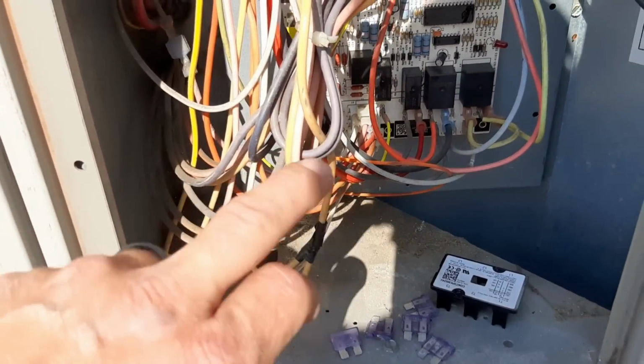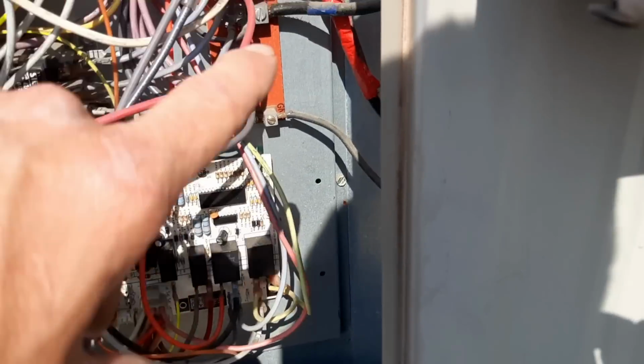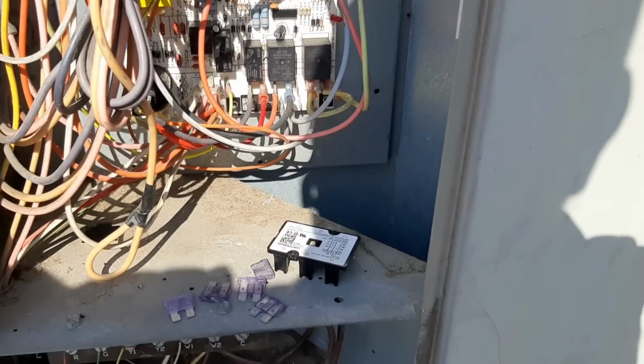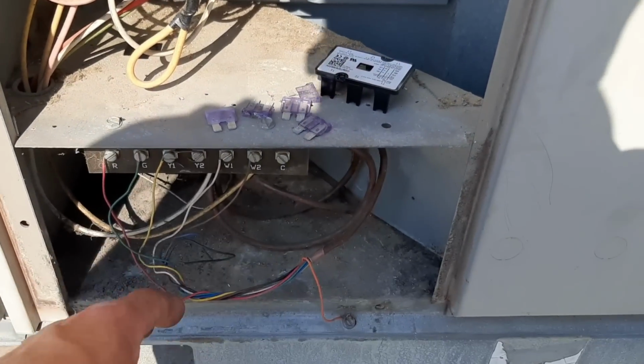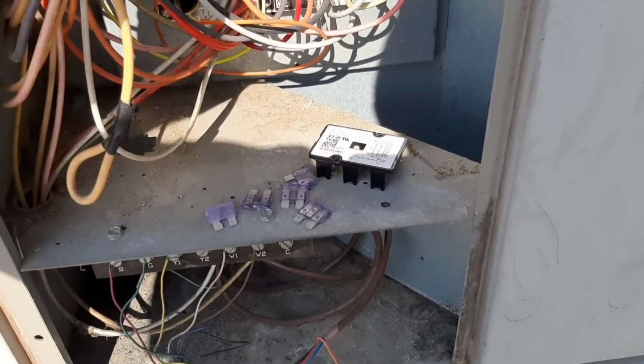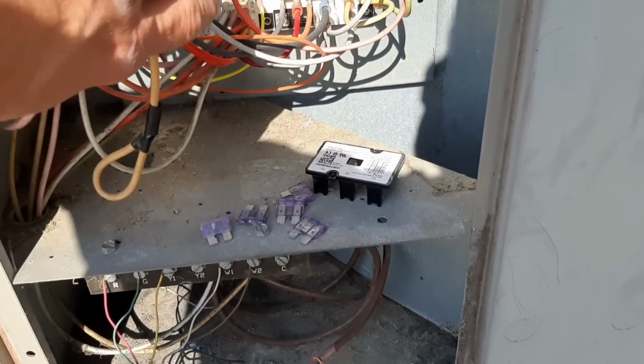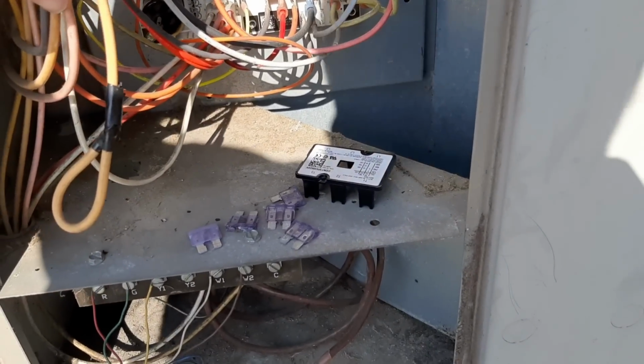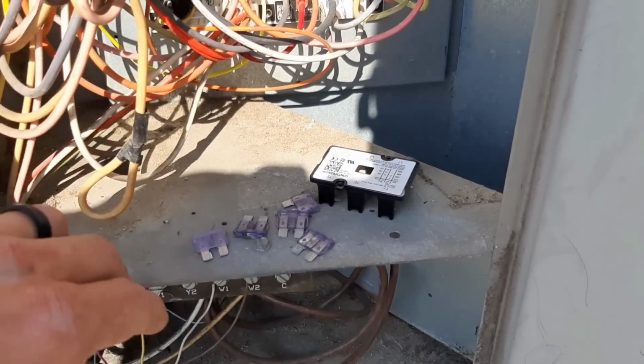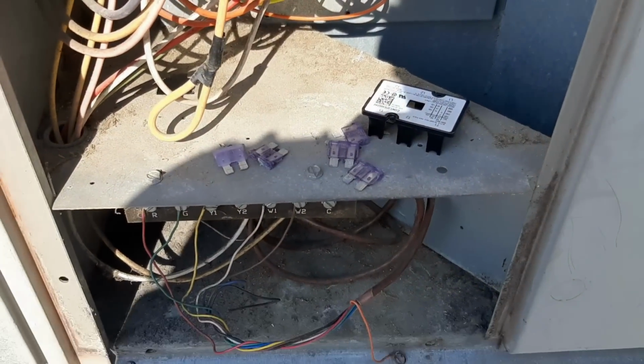So I probably do have high voltage, so I ought to be careful. We'll check for that in a minute. Let's kill the power and find out where our short is, and see if we can't locate something that's caused 5 fuses to trip.